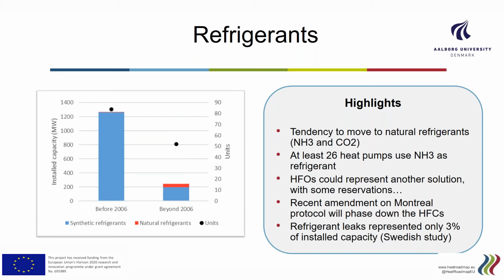Carbon dioxide. It's a refrigerant which is non-toxic, non-flammable, and non-corrosive, and is generally obtained as a waste product, making it quite a cheap refrigerant. However, the downside of this refrigerant is that it has to work at high pressures, making it less suitable for large-scale applications. And here I mean larger than 1 to 2 megawatts thermal. There's only one example of a large-scale heat pump using CO2 refrigerant in the survey, and that is in Denmark, in the Marstal district heating network, and it has a heating capacity of 1.5 megawatts.